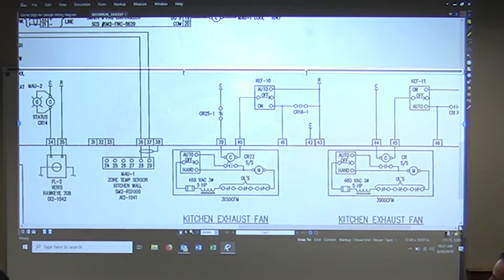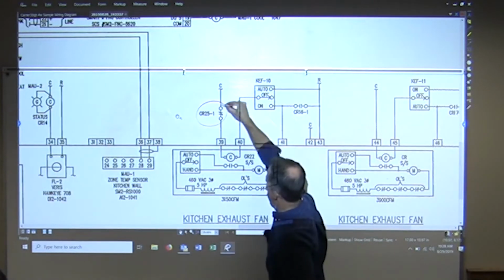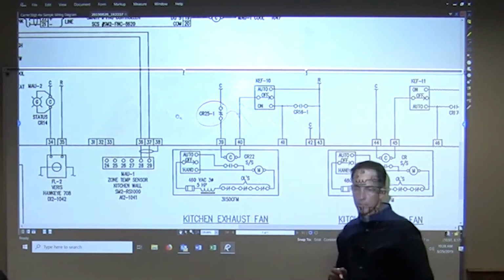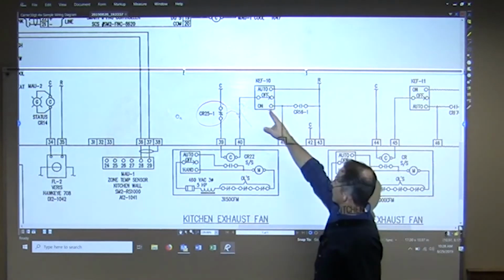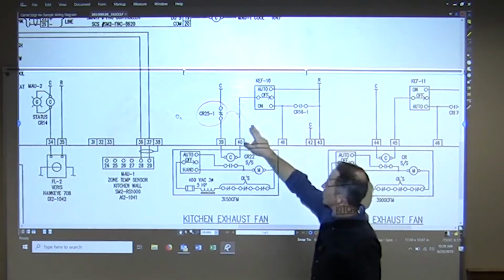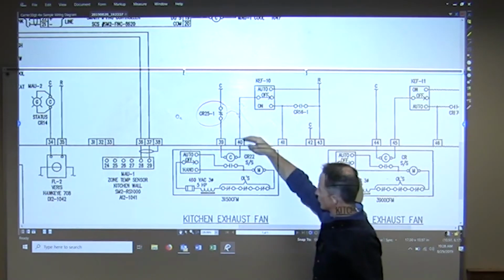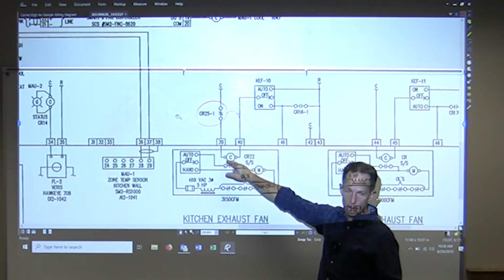Really, CR25 is in a normal closed position, right? So it's always providing power to that exhaust. Yeah, so it's going to take power to disable it, and I think that's okay. Let's assume that the functionality of the contact is correct. As far as where this contact is, where might be a better place to have put that instead of in the common side? On the R side of the tower. Okay, so if we were to take this and just put it right there, then our hand-off-auto switch, our automatic enable switch, our safety interlock is all on the switched leg going out to that relay.